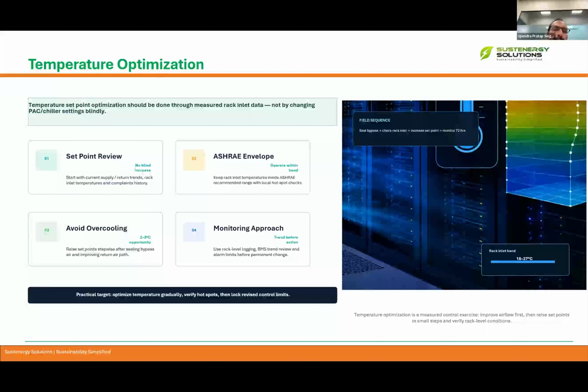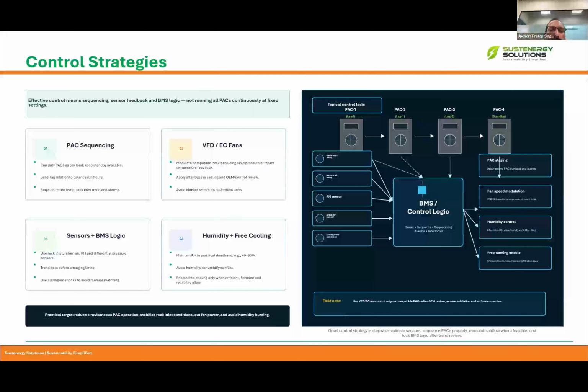And then we have to avoid the overcooling. So this gives at least 2 to 3 degrees centigrade opportunity for optimizing the cooling. And then we have to do the proper monitoring. You have to do it at the rack level, then trends in the BMS. So these parameters are important to optimize the temperature and subsequently reduce the cooling power.